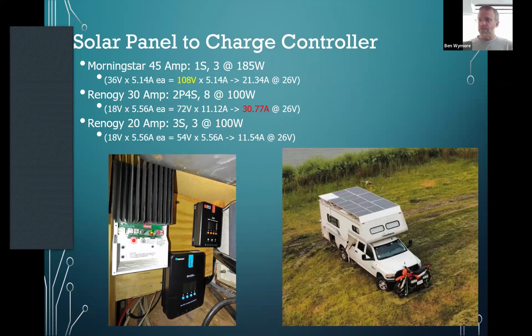When the controllers stop, they decrease their current. With less current going through, the voltage drop decreases, so the system thinks the battery's not quite full and starts up again. Practically speaking, the amount of current tapers off, but way too early, like at 60% charge, when I want the battery at 80% charge.